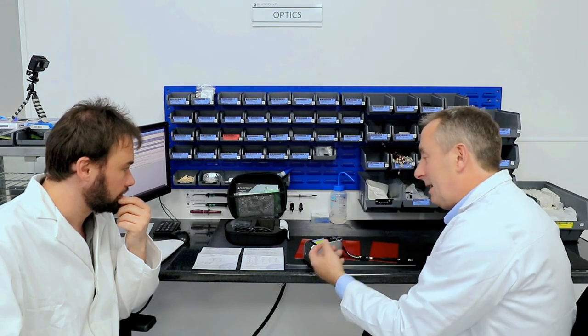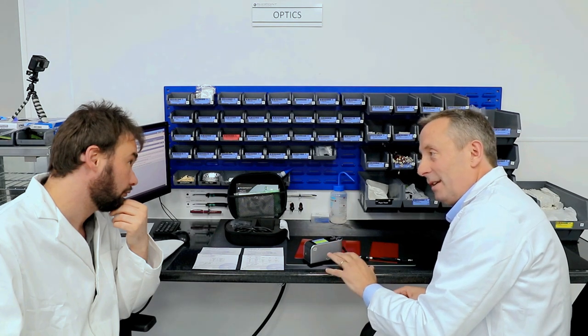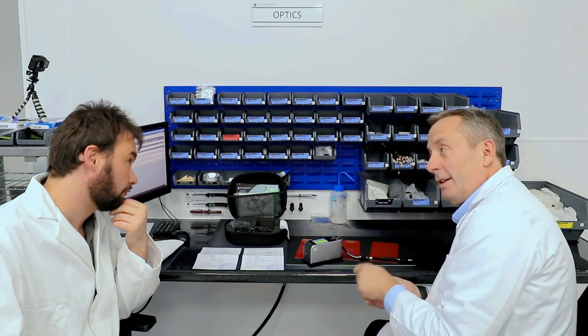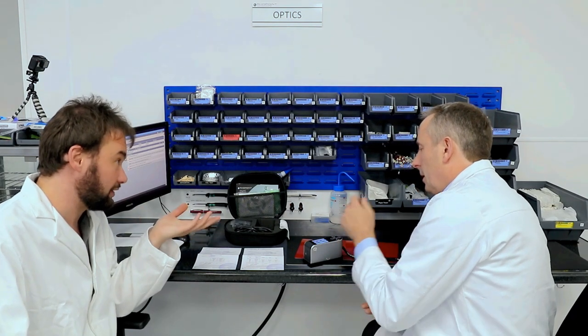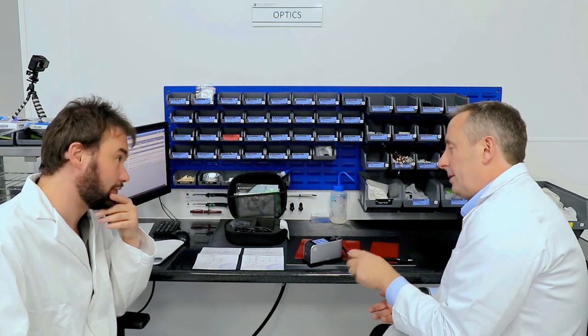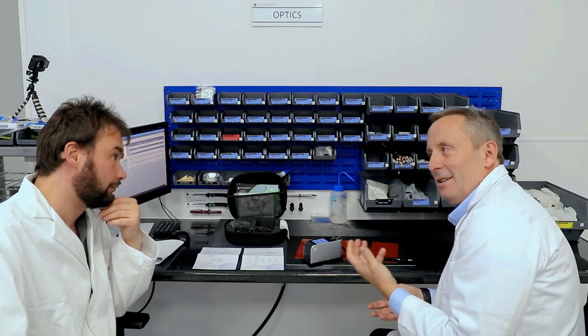And also it'll actually detect if the calibration artifact's dirty or any fingerprints. It's good to have a quick look at it and then have a polish before you do as well. Out of interest, what's the cleaning regime for that piece of glass? Is there any particular chemicals you use on it? No, so we sell it with an optical cleaning cloth. Just please don't dunk it in anything horrible or get it too dirty because it's not so easy to recover, but optical cleaning cloth, anything you'd use to clean your glasses. We want it to be perfectly smear-free.